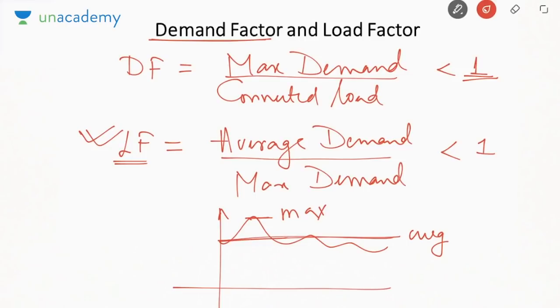So that means the capacity of the power system should always be greater than the demand. So that means the capacity should be greater than the maximum demand. Okay. So that even we can meet the maximum demand in a power system. Now if you have to keep a high capacity, then the cost of the system will be high. So if maximum is equal to average, then maximum demand will be lesser. That means the capacity required will be lesser. That means the cost of the system will also be lesser. So from an economic point of view, it is always better that the load factor should be as close to unity as possible. Okay, that will reduce the cost of the system.